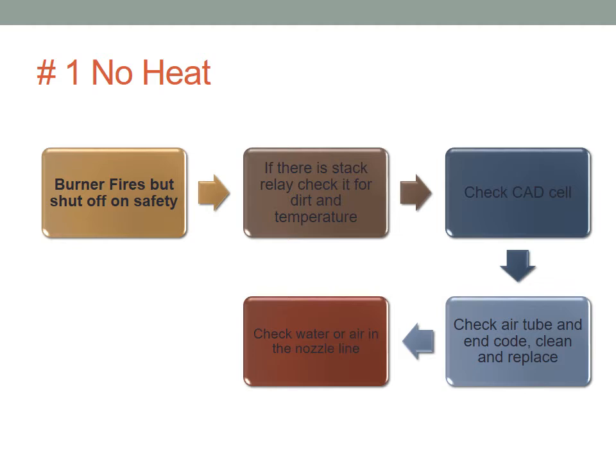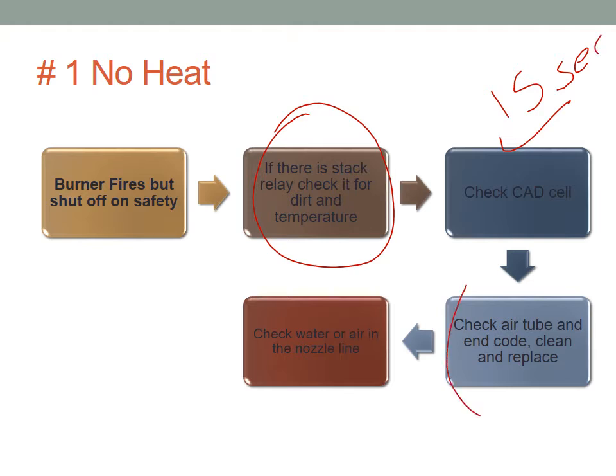Okay, what else? Another case, if the burner fires but shuts off in safety, that happens a lot. So we have fire, then it goes away, and we had that actually before spring break with a couple of the students. We tried to turn it on, it turns on, then it goes away. Check the stack relay is functioning correctly, and the contacts are made completely. If they're not made completely, something is wrong with those contacts that disconnects. Check the CAD cell, because within 15 seconds, if it doesn't see the light, it will go out. So that could be a problem. Check the air tube, clean or replace. That's where we have air coming to the motor.